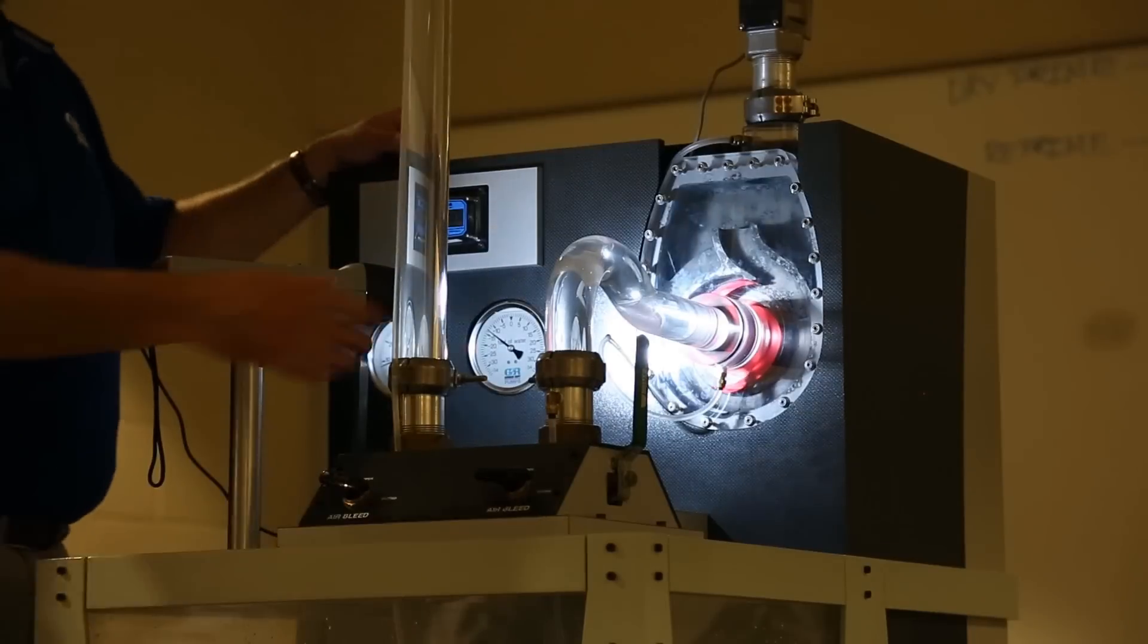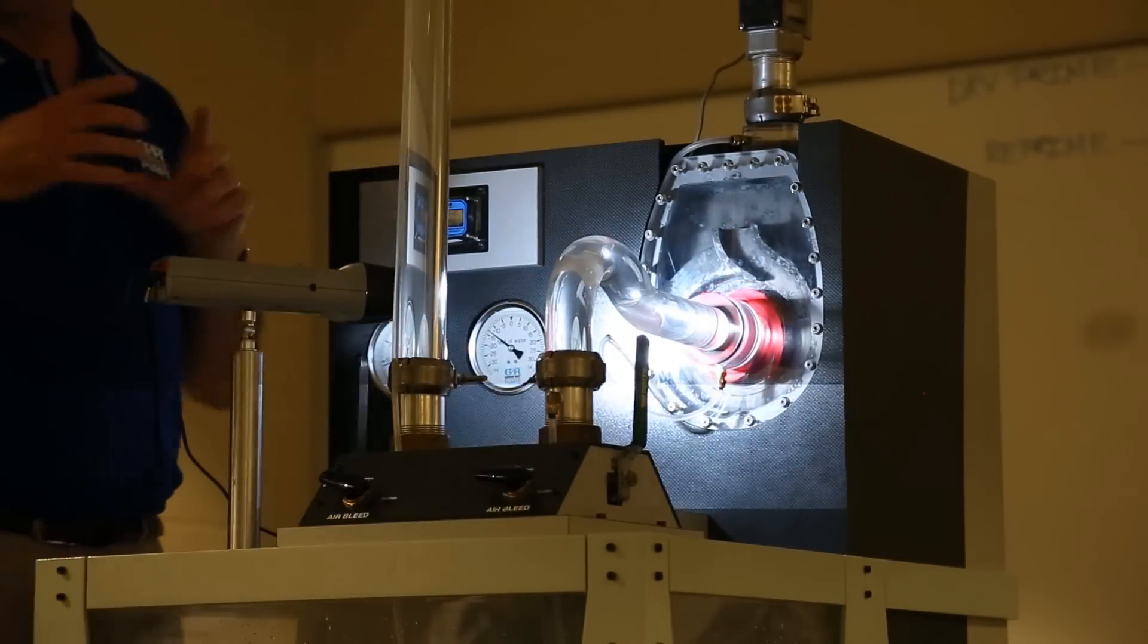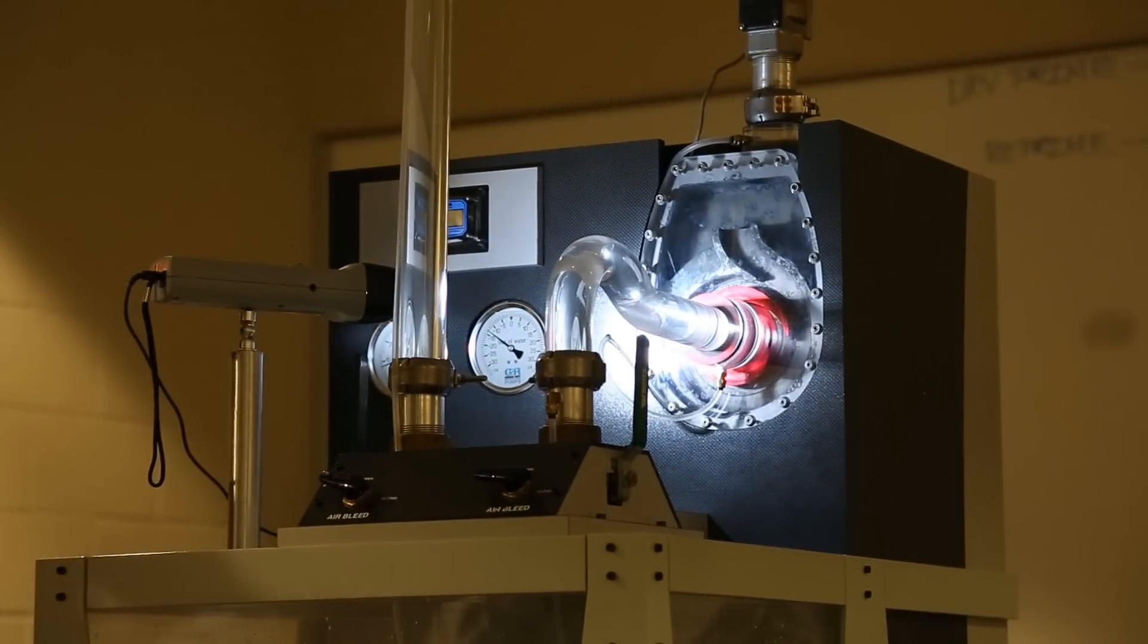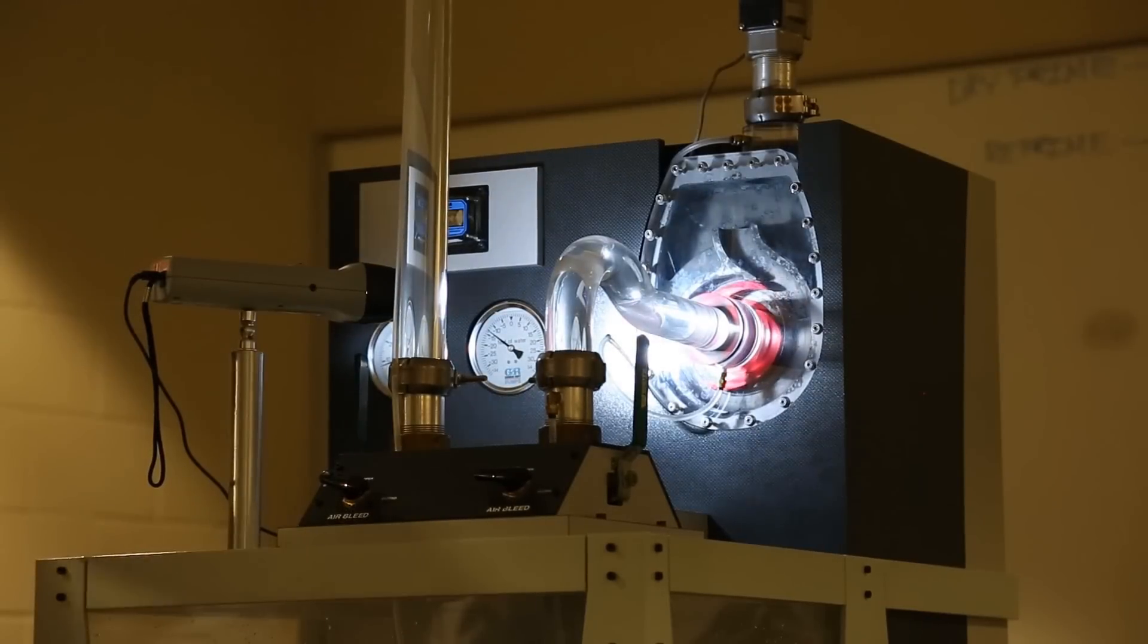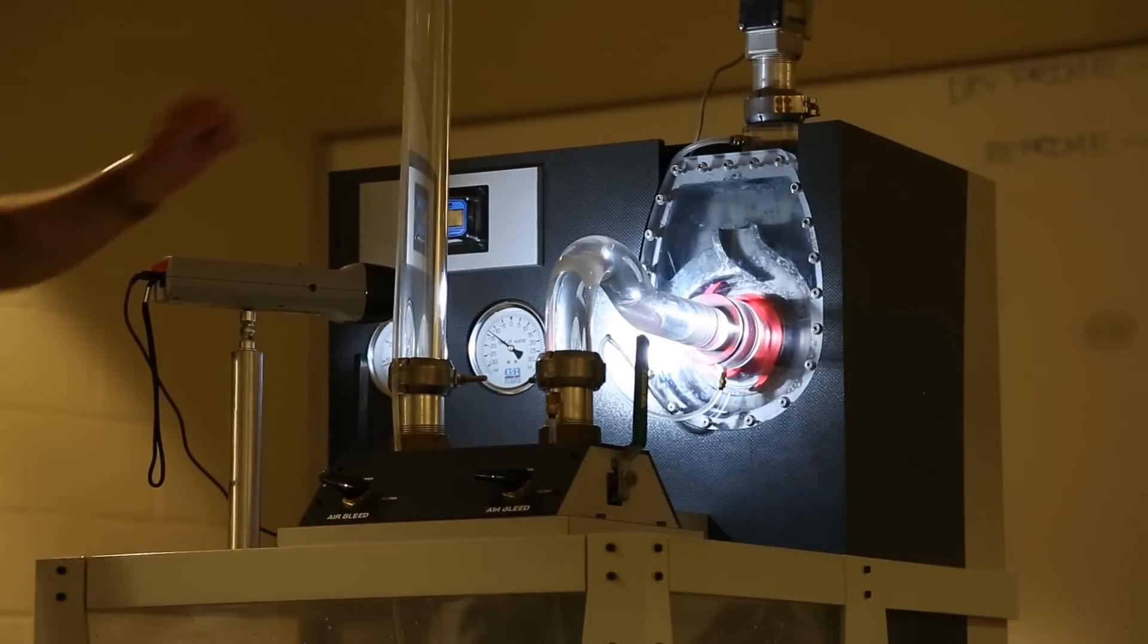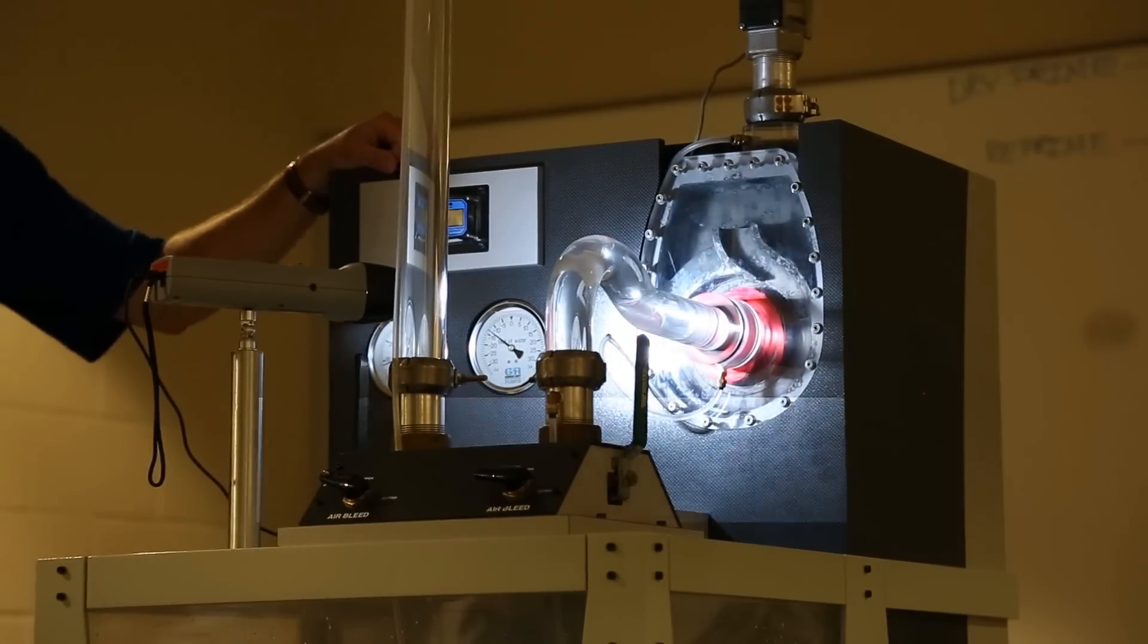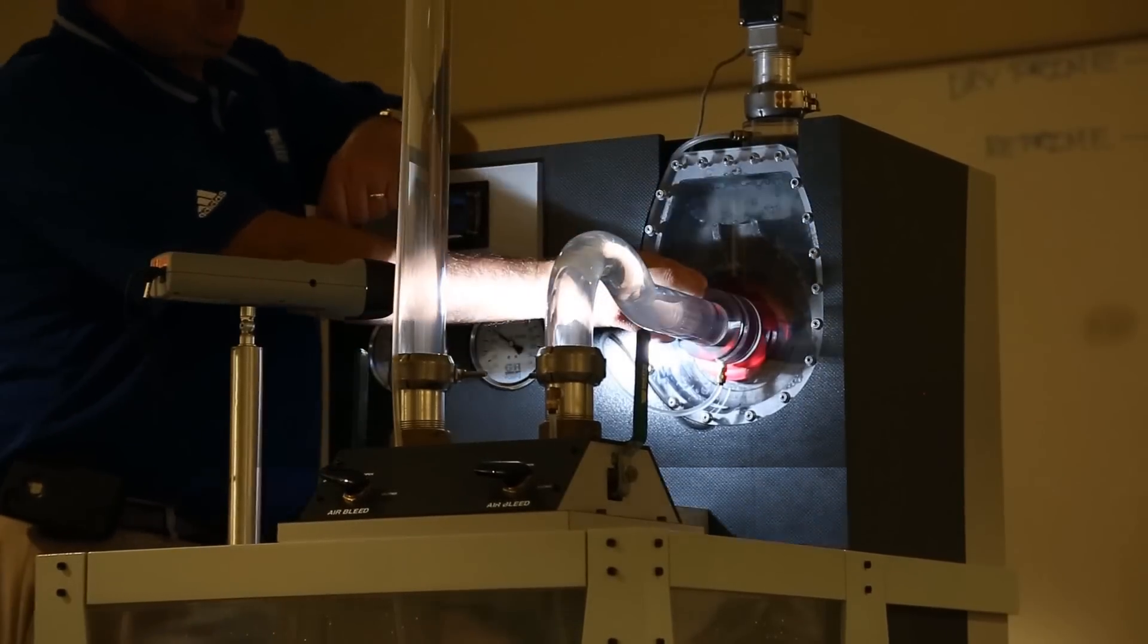And that's what we're doing. I've got about 69, 70 gallons a minute going through an inch and a quarter opening. As I start to close that opening down, the liquid has to go faster and faster to get through that small opening. So as the velocity of the liquid goes up, the pressure goes down. The liquid can't stay in a liquid state, it flashes to vapor.